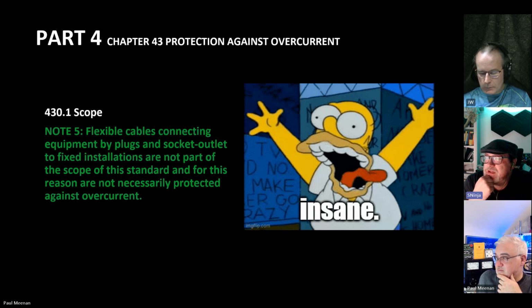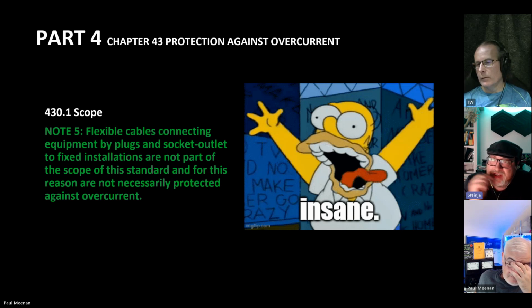I think what it means is anything that's on a cord set that's plugged into an accessory like a 13A socket, there's a fuse there, so the overcurrent protective selection requirements of that cord set aren't necessarily within the reach of 7671, as the overcurrent protection is in the construction assembly of the product that the plug and cord set is attached to.